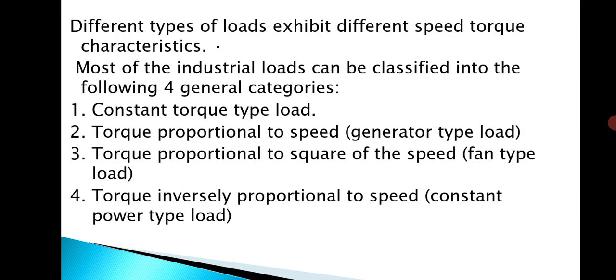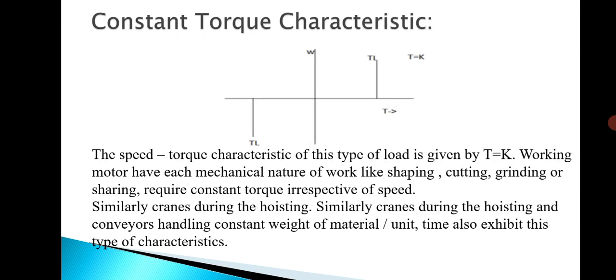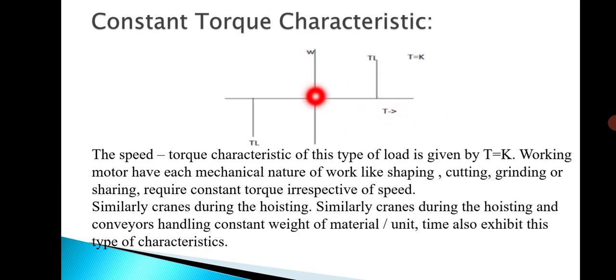The first is constant torque characteristics. The speed-torque characteristics of this type of load is given by T equal to K. You can see that the torque is always constant with varying speed — torque versus speed is constant. When the speed is varying, the torque will always be constant. Working motors with mechanical operations like shaping, cutting, grinding, or shearing require constant torque irrespective of speed.